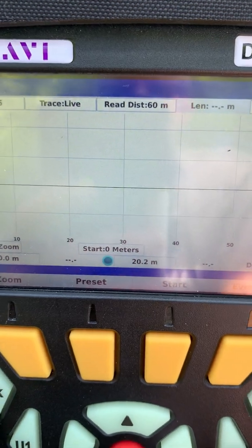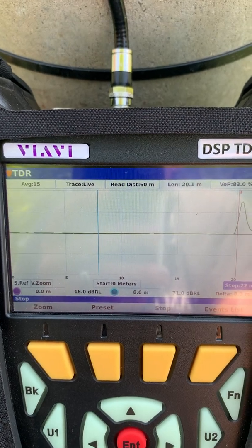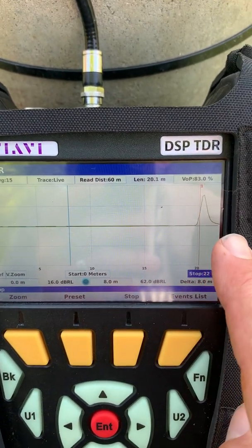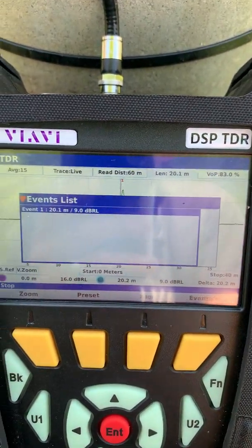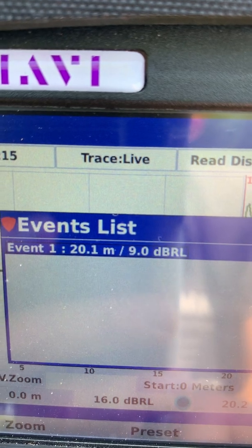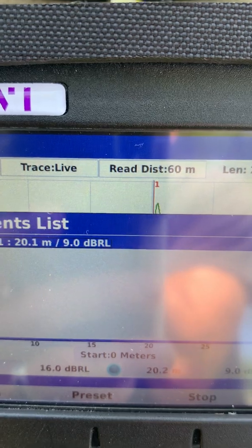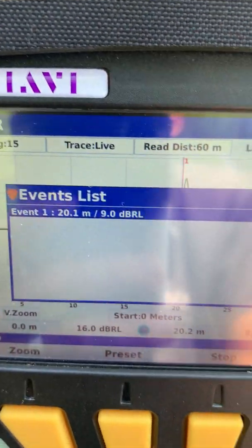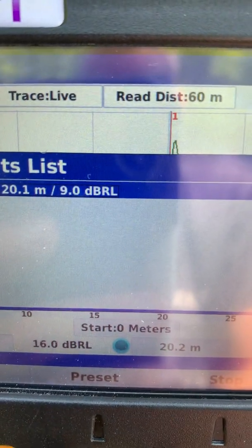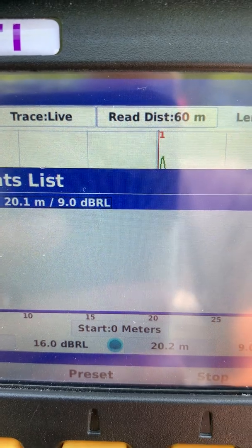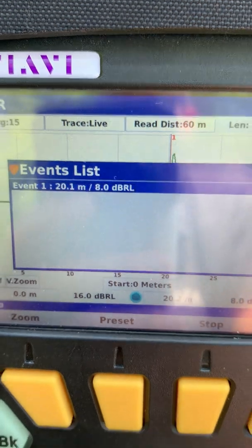With everything set up, all we have to do is hit start. Right away it's found a fault. To check exactly how far that is, we hit Events List — and it says the fault is at 20.1 meters. You'll also notice the dBRL reading — decibel return loss. The closer to zero that number is, the bigger the fault. Here we have 9 dBRL, meaning it's a fairly large fault. If it's 30 or 40 dBRL, it's actually a smaller fault — so keep that in mind when reading dBRL.